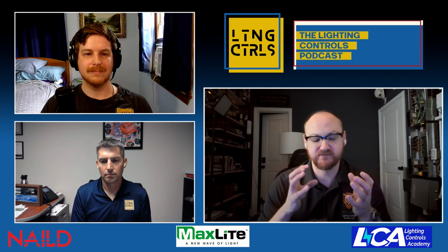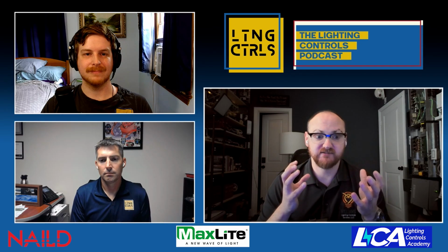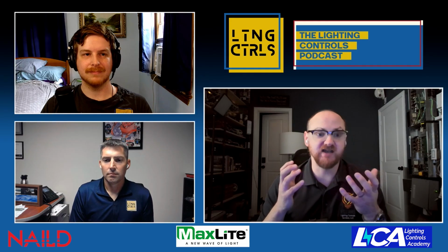Luckily, hopefully not, and then I go from there. I've got a good chance that 99% of the time that's a safe bet, covering myself by doing little spot checks like that, checking to see if I have a green or blue flashing LED for ultrasonic, or a red flashing LED for passive infrared, and whether I can stand perfectly still without false triggering it while nobody's moving around me.